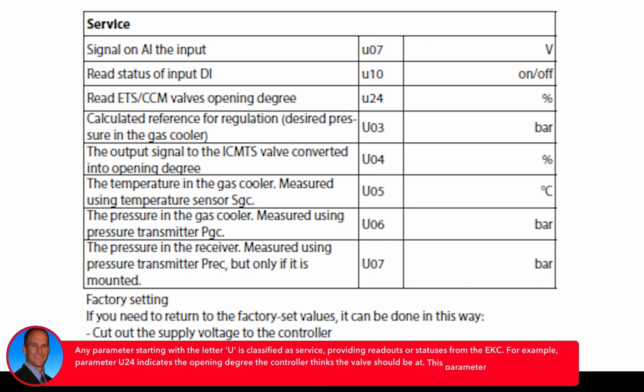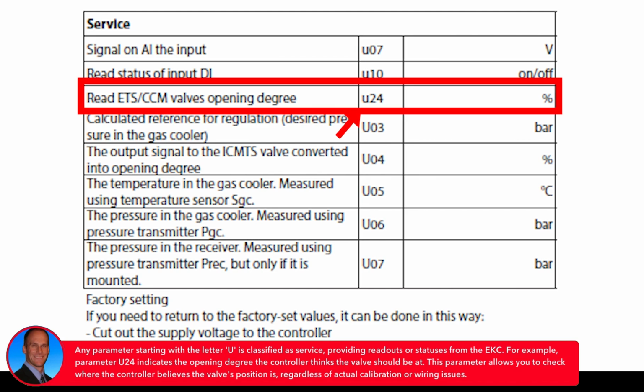This is from our user guide on the EKC. We won't look at all the parameters here now, but one of the things you can see for someone that's scrolling through the parameters, using those 2 buttons right there at the controller itself, is that any parameter that starts with the letter U is classified as service, but it's basically readouts or statuses from the EKC. So a parameter like a U24 here would tell us in the EKC what opening degree we think we're telling the valve to be at and that it should be at. And yeah, obviously with stepper valves, calibration can come into play, but in terms of where the controller thinks the valve's at, this U24 parameter would give you that value.